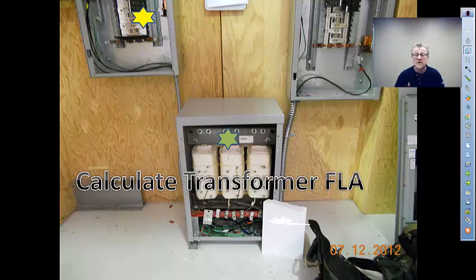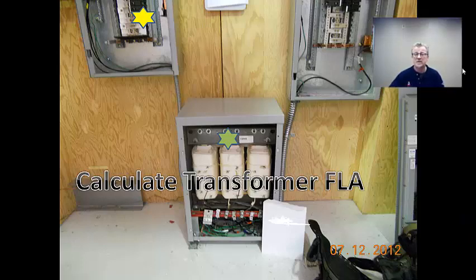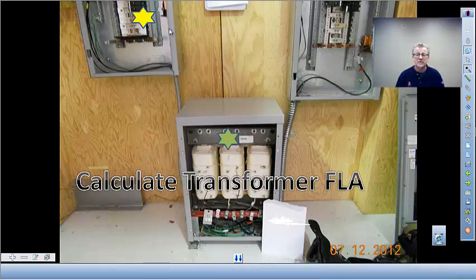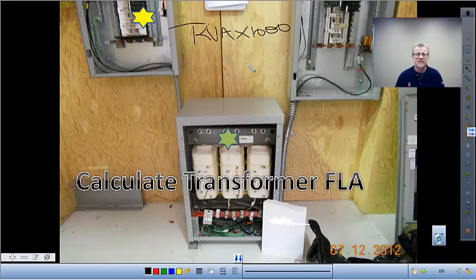Full load current is going to be calculated, if I can find my mouse somewhere on the screen, I'll get us writing: transformer FLA. Take the kVA and multiply by 1,000. That gets rid of the K, and you have volt amps. Take volt amps and divide it by volts, you'll get amps. And if you use the square root of 3, that is a constant for three-phase systems.